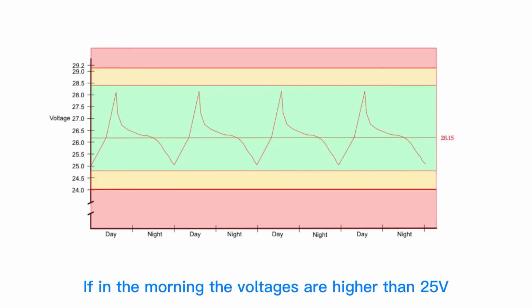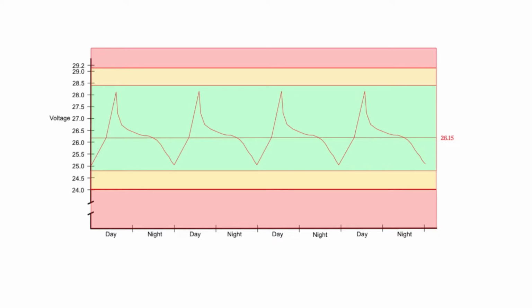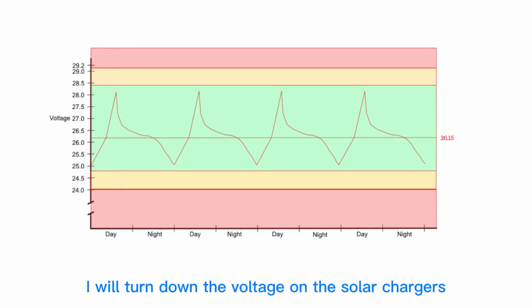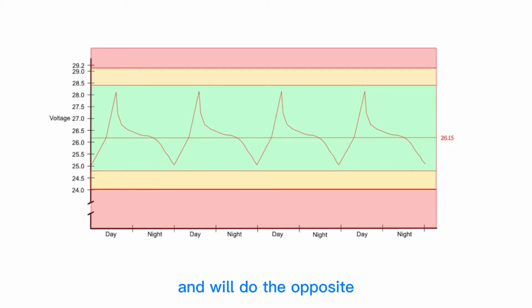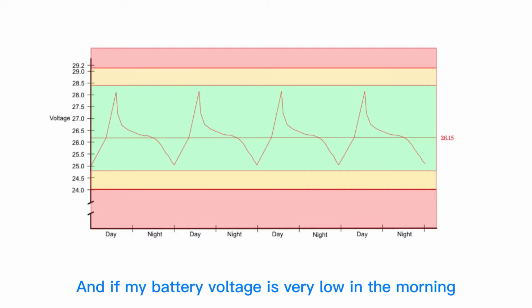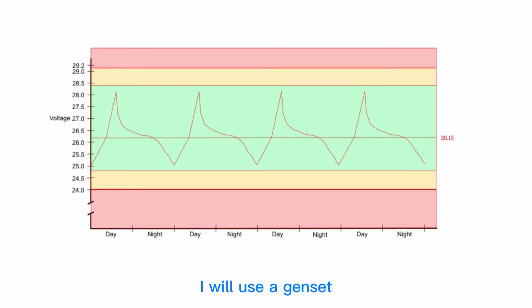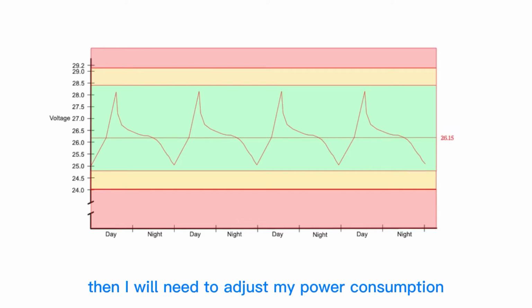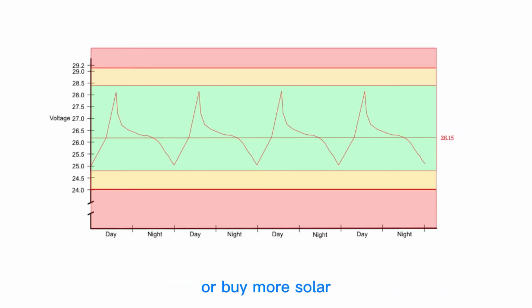If, in the morning, the voltages are higher than 25 volts before the solar starts charging, I will turn down the voltage on the solar chargers, and will do the opposite if the voltage is lower than 25 volts. And if my battery voltage is very low in the morning, I will use a genset. If the voltage is always low, then I will need to adjust my power consumption or buy more solar.